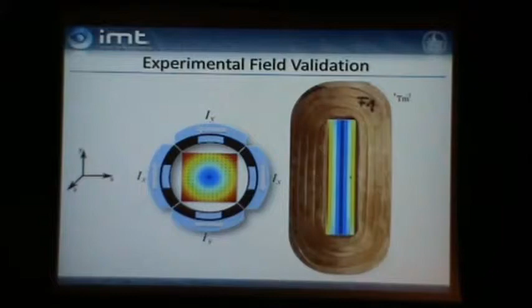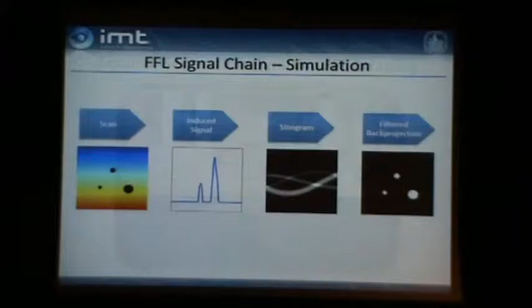Okay, and this is now able to rotate and translate and produce a field-free line. Here you see the complete setup of this machine, and for example here some of the sophisticated receive coils that we produce. What we have now here first in simulation is the situation as we know it from CT. We have a field-free line running over the distribution of nanoparticles, and we always receive the sum of all magnetization changes. This produces a sinogram, and from the sinogram, by filtered back projection, you can then receive the image, the distribution of the nanoparticles.